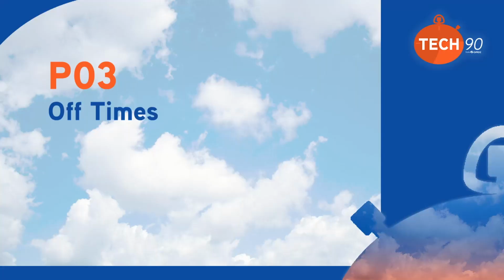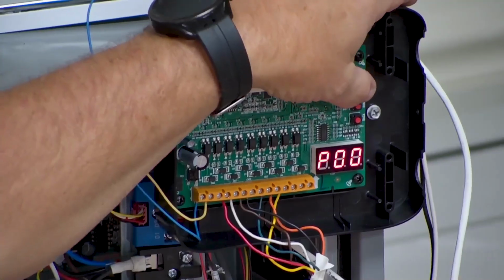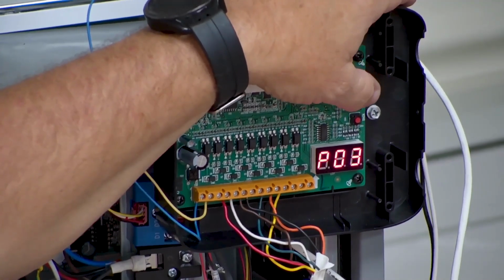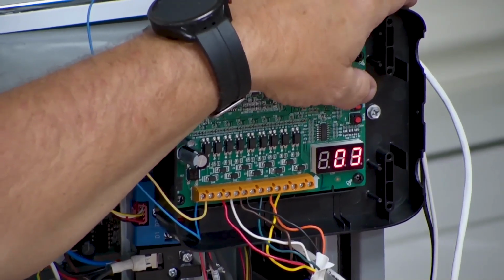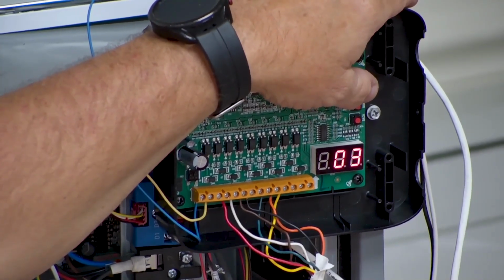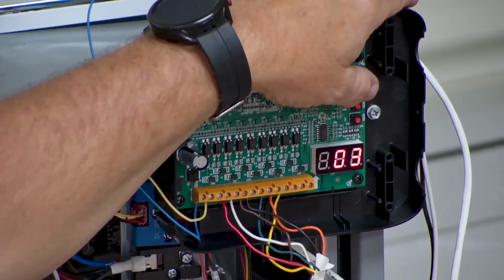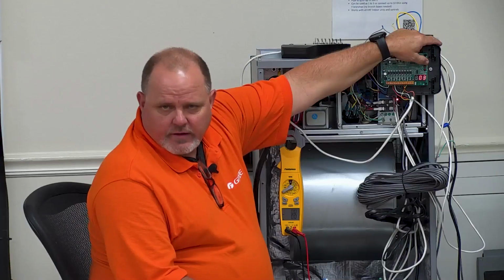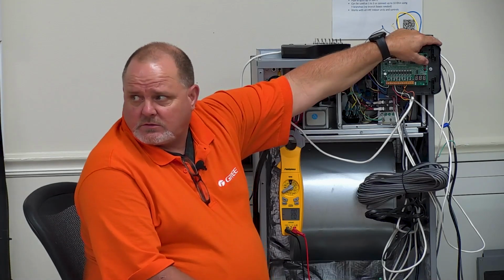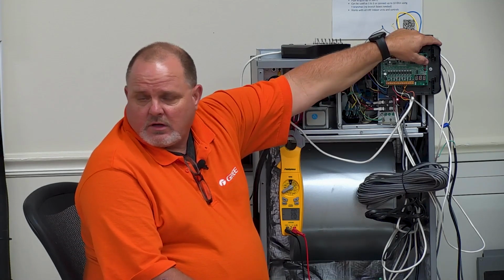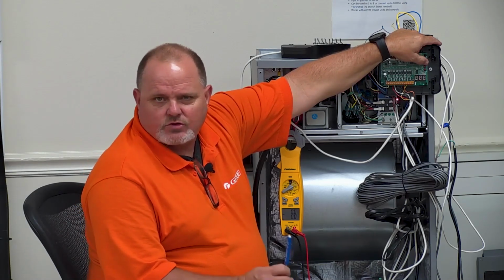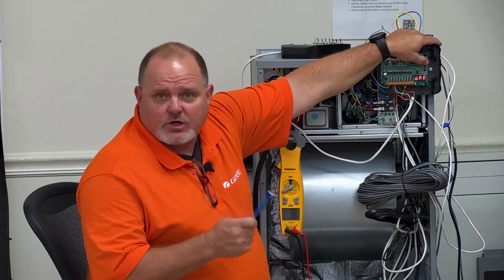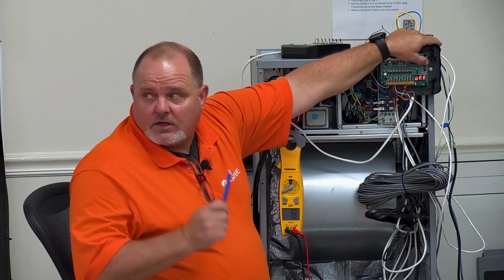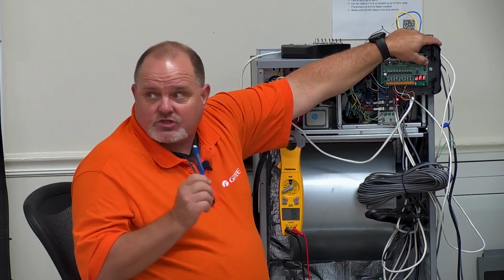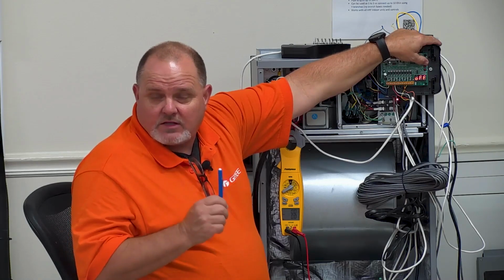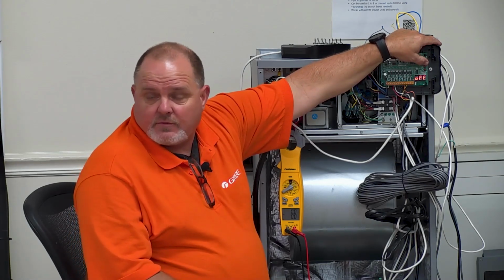So again, now we're going to go with P03. So there's P00, P02, P03. Enter. And these are our off times. You got 00. 00 is 5 minutes. Okay, and 01? 01's 10 minutes. 02 is 30 minutes, and okay, 03. So that's what we changed though. So on the new production one, 00 is going to be 0 minutes. 01 is going to be 5 minutes. 02 is going to be 10 minutes, and 03 is going to be 20 minutes.